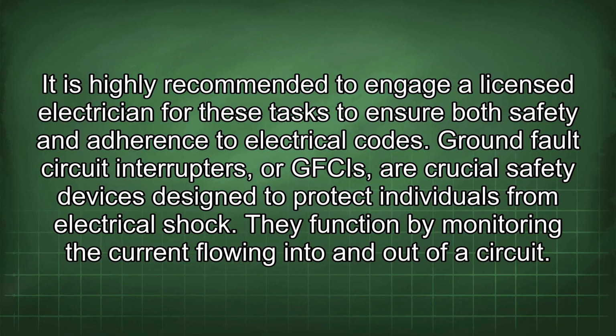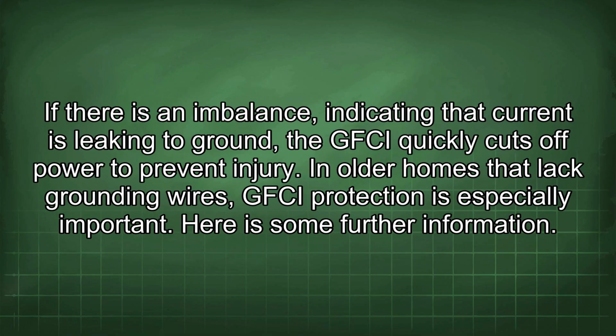Ground fault circuit interrupters, or GFCIs, are crucial safety devices designed to protect individuals from electrical shock. They function by monitoring the current flowing into and out of a circuit. If there is an imbalance, indicating that current is leaking to ground, the GFCI quickly cuts off power to prevent injury. In older homes that lack grounding wires, GFCI protection is especially important. Here is some further information.